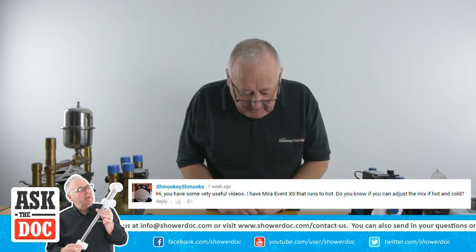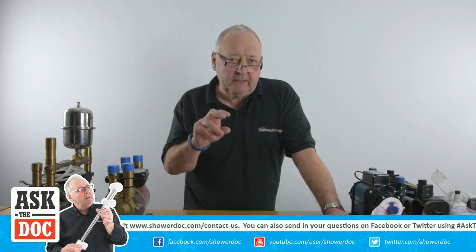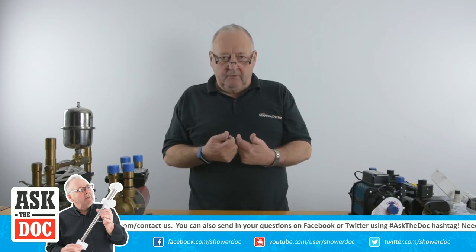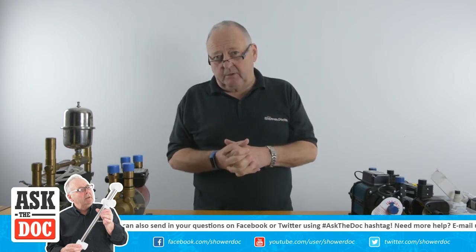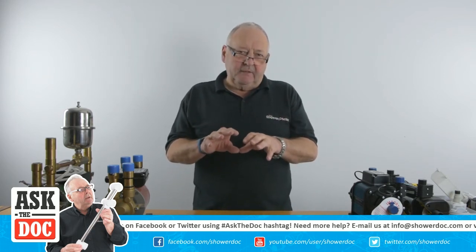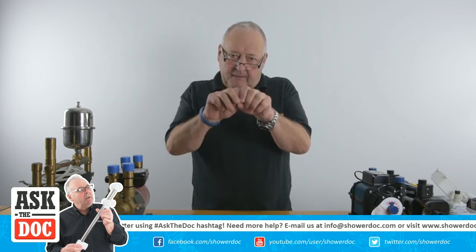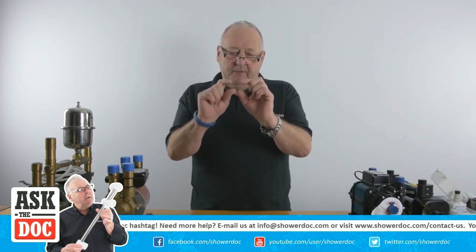I have a Mira Event XS that runs too hot. Do you know if there's anything you can adjust to mix the hot and cold? Well, there is a mixing valve inside the XS, but probably the first thing to look at with the Mira XS is the inlets — there are two filters. It may be that the filters are blocked. If there's not enough water getting through the filters, then it's probably not able to balance the water properly, and that may be why it's running hot. It could be the valve itself causing the problem. There are two types of mixing valve in there: a manual mixing valve and a thermostatic mixing valve. If it's faulty, it's likely to be the thermostatic mixing valve. But whatever you do, the first thing is to check the filters, because that costs you nothing. Turn the water off first, unscrew the cap, and there are two filters inside — they're like little pipes. If they're blocked, that's where your problem is.